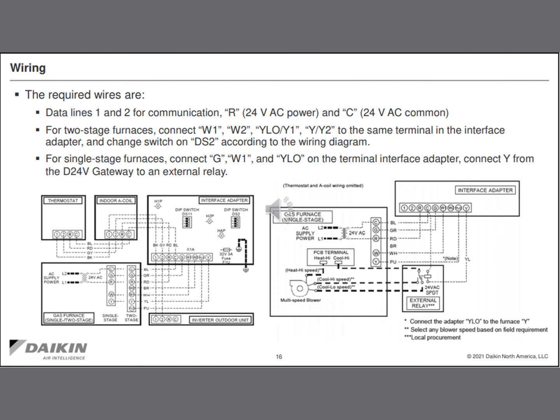Now, when you are using this in a single stage gas furnace application, you will see that there is an external relay that Daikin will want you to add. The purpose for that relay is so that we can split our cooling speeds between a high cool profile and a low cool profile. Remember, we still have an inverter driven compressor that has different airflow requirements, so we split that into a high range of airflow and a low range. And when we have that external relay on there, we can switch between a high speed cooling or a low speed cooling application, it'll really help control our capacity and our dehumidification. Two-stage furnace, we don't have to worry about that because we already have the multiple blower speeds built into the furnace.